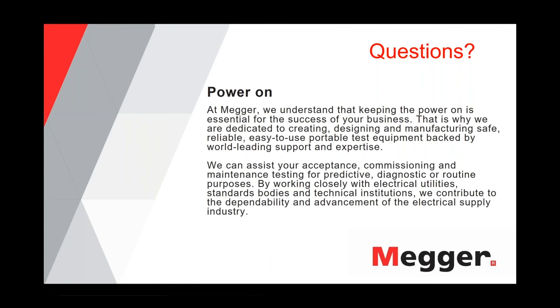All right. Robert, is tan delta a worthwhile test for EPR cable? Does EPR cable fail by water treeing? So the answer is yes and yes. Obviously, you can do tan delta on EPR cables. The guideline, IEEE 400.2, has different tables for different insulation type cables. And yes, EPR cable does tree. That's actually been known for quite a while. There are papers on that. It is not free from water treeing.